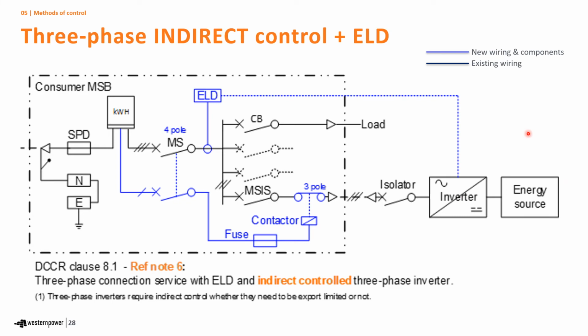Now the next example is, again, indirect control, but with an export limiting device. Essentially the same arrangement. However, you have an export limiting device measuring net generation and net load at the 3 poles of the main switch. The other pole is sending the disconnect signal to the contactor to disconnect or reconnect the inverter.